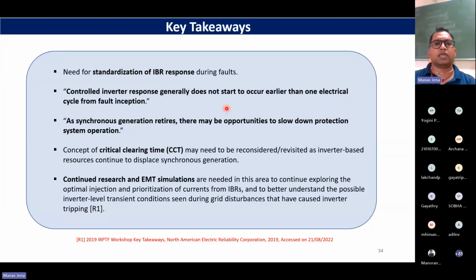Controlled inverter response generally does not start to occur earlier than one cycle from fault inception. We just saw that, you are connecting the inverter, you have the measurement of the terminal voltage based on which you are deciding your ID ref and IQ ref. So if there is some issue, you are sensing the voltage, you are changing your ID ref and IQ ref to support the grid, absolutely fine. But what is the response time? How quickly you are changing your reference, and how quickly your actual quantity is following or tracking the reference quantity.